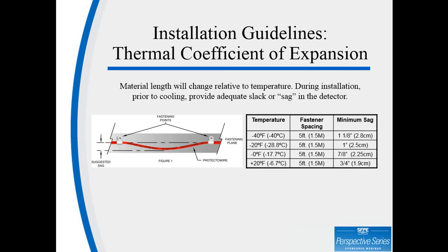LHD installation guidelines, thermal coefficient of expansion. One of the things the designers and the installers have to consider is that this product is made from steel wire, which expands and contracts with temperature. In many cases, for instance in the case of a freezer complex, they may be installing the detector at 70 degrees or even higher.